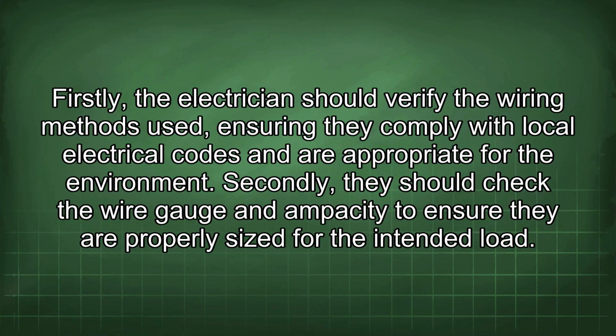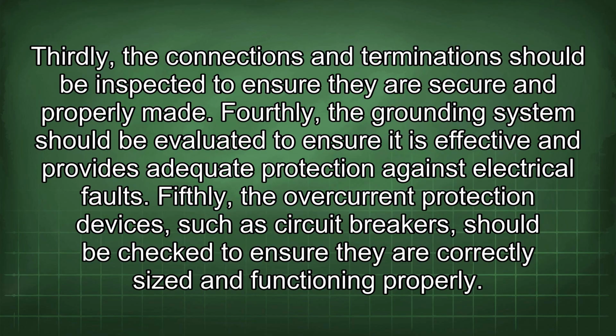Firstly, the electrician should verify the wiring methods used, ensuring they comply with local electrical codes and are appropriate for the environment. Secondly, they should check the wire gauge and ampacity to ensure they are properly sized for the intended load. Thirdly, the connections and terminations should be inspected to ensure they are secure and properly made. Fourthly, the grounding system should be evaluated to ensure it is effective and provides adequate protection against electrical faults.